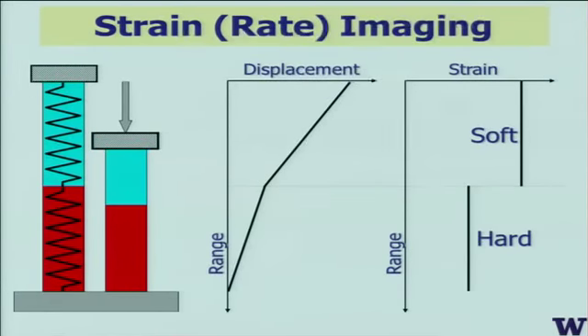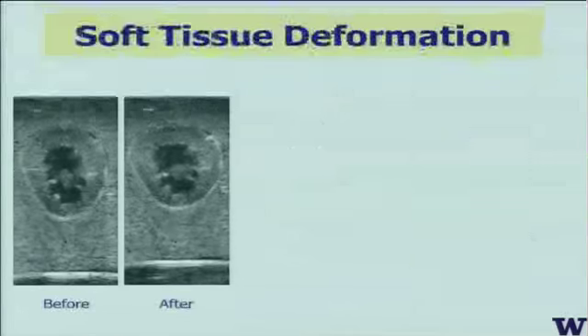And the idea is, of course, the most simplistic idea in 1D: if you have two springs and one's hard and one's soft, you put a constant displacement on there, most of the displacement will be soaked up in the soft material and less in the hard material. So if you can make a measure of the displacement point by point by point and take a spatial derivative, you have something which is directly related to the mechanical characteristics of the material. Okay, so how do you do that in an imaging system?